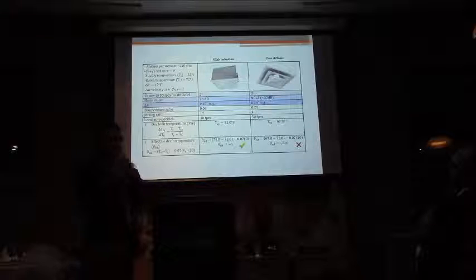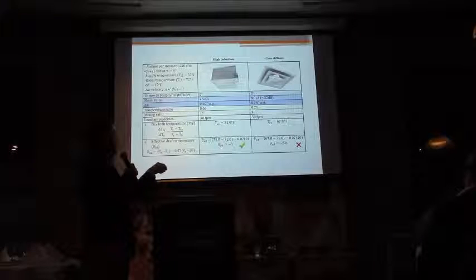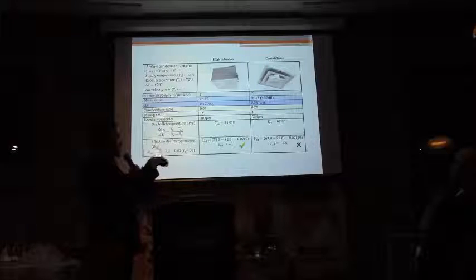It might not be everywhere across the room fail, but at this particular spot, the most critical spot of them all, the cone diffuser would fail. While the high induction has a pass, and a very good one, because anywhere between -3 and +2 is a pass, and it's right there in the middle. So it's a very good pass, in fact.